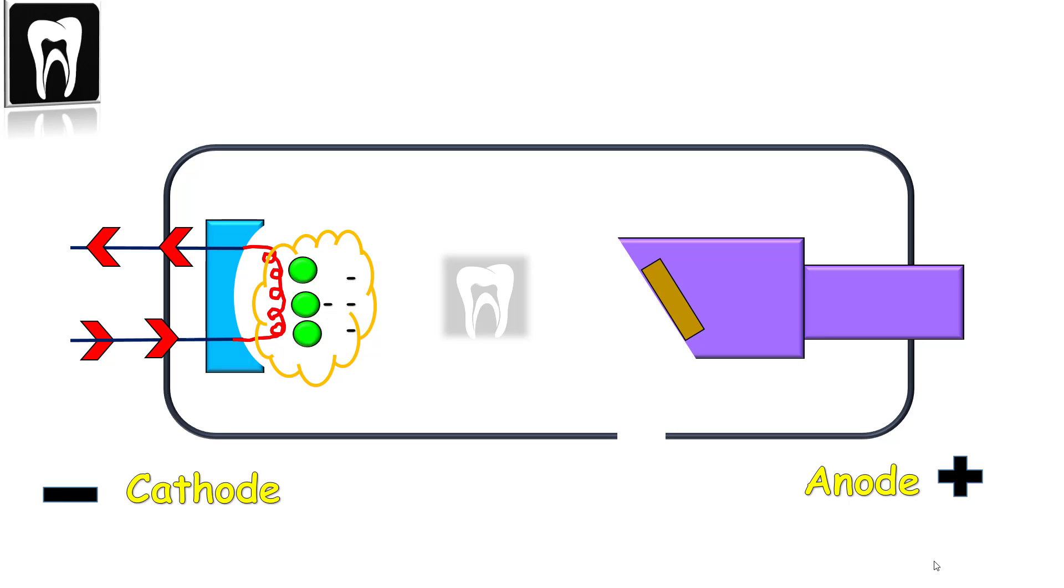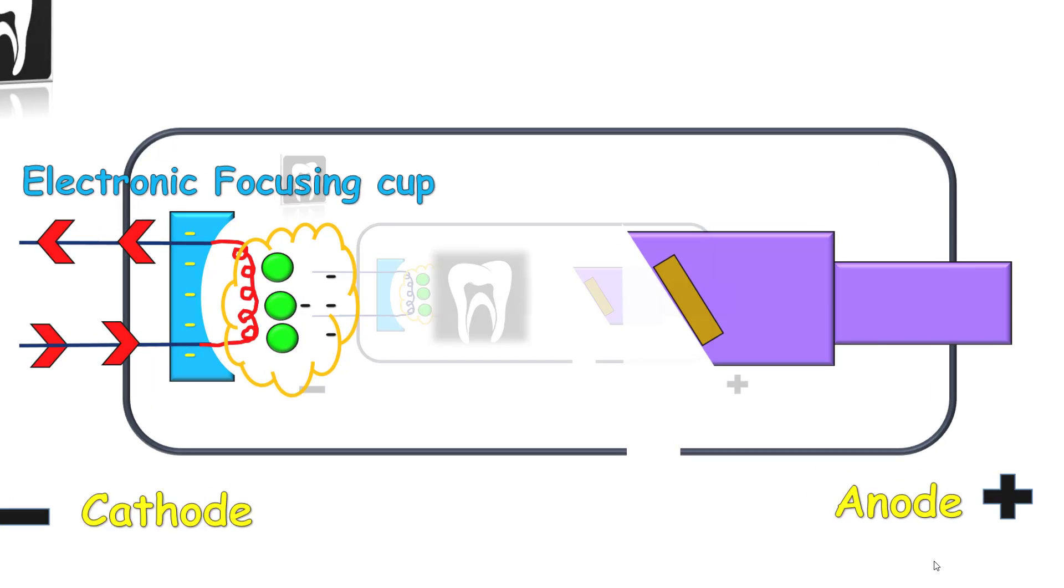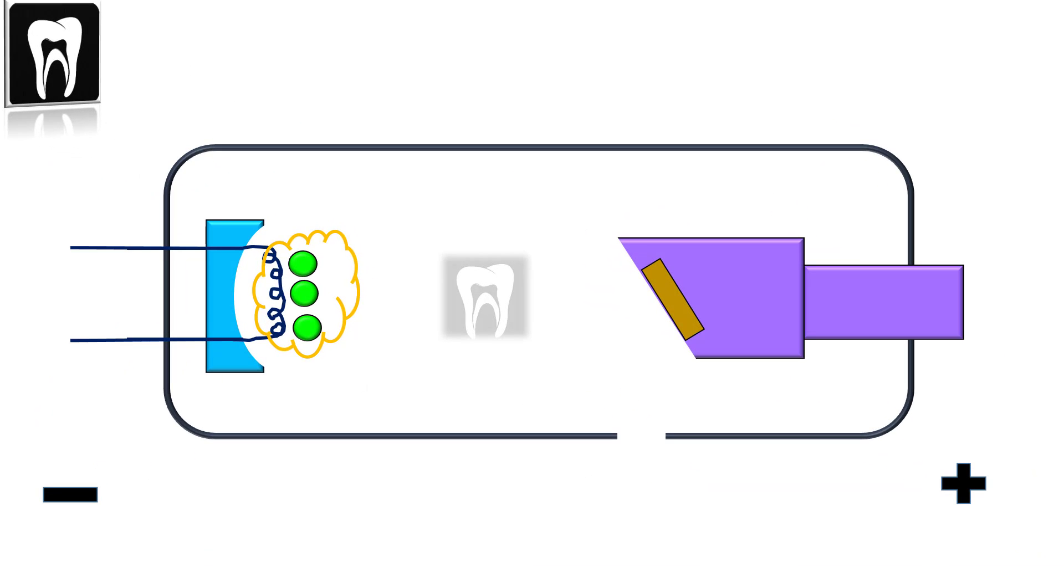Another part in the cathode is the electronic focusing cup, made of molybdenum. It's a negatively charged concave bowl that focuses the electrons into a narrow beam toward a small area on the anode, contracting the width of electron distribution.